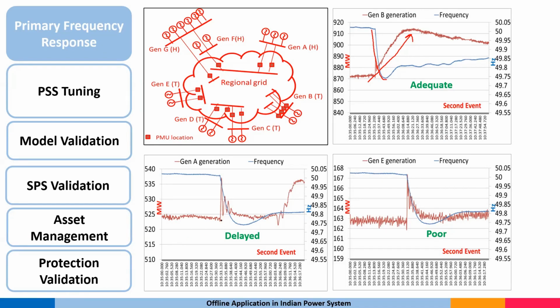So this also we are able to monitor, because these are sub-second information. So we are able to capture where the problem is. Here you can see that it has provided the initial change in the generation, but it has suddenly become zero, reduced back to its original position, and later on it has provided with a delay. Here it has not provided at all; it has increased and suddenly decreased. So we provide feedback to the generator to tune their parameters, tune their generator control, so that they can provide the proper frequency response for the grid operation or reliability of the grid.